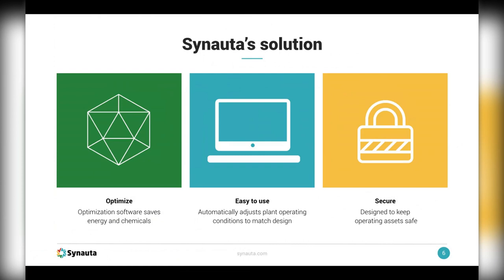The solution we've put together is based on artificial intelligence — machine learning is a subset of that. The optimization software that Synauta built saves energy and chemicals. Our first focus is on energy, particularly at large seawater plants, because our basic equation is: the saltier the water, the more energy it takes to desalinate — because of the osmotic pressure that needs to be overcome even to make one drop of fresh water. Large plants also clean their membranes using chemicals, so we can optimize when and how much chemical they use.